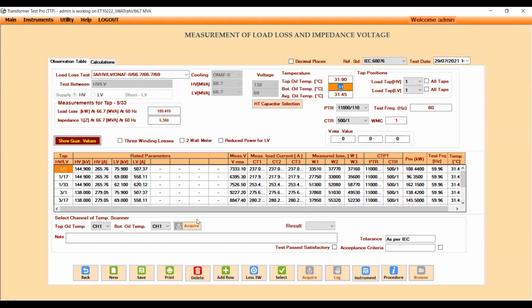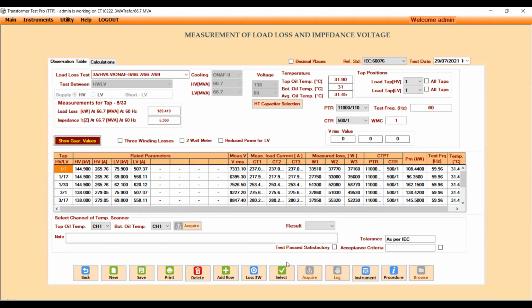While conducting this test, it is very important that most of the places we make use of HT capacitor banks, because it is always advisable not to draw the whole power from the mains, and that's where HT capacitors will be used. And this chart will give you the information as to how many HT capacitors are to be put in circuit for the given rating of the transformer automatically, so that you don't have to calculate or worry about anything, and it will help you quickly finish your load loss and impedance measurement test.